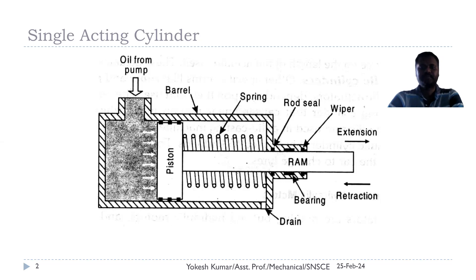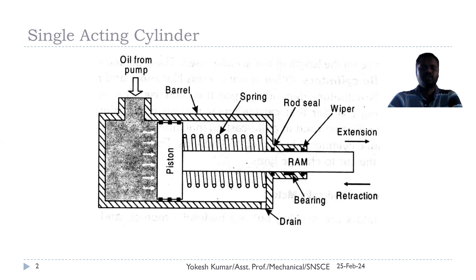The piston is connected with the ram, which makes linear extension and retraction motion. On the other side of the barrel, we have a spring mechanism, and retraction is ensured with the help of this spring. The left-hand side of the piston is the blank end and the right-hand side is the rod end. The ram reciprocates with the help of rod seals and wiper seals. Bearings are also present. The purpose of the rod seal is to avoid leakage of oil from inside the cylinder to outside, and the bearings are used to reduce friction.